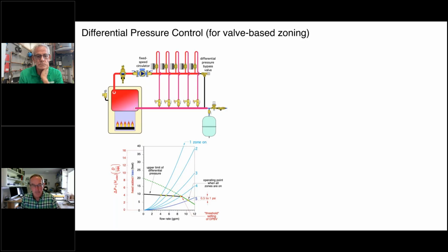We've been in projects where we could literally hear the noise through a zone valve outside a mechanical room with the mechanical room door shut. It was just buzzing or singing away. And obviously you don't want that. So one of the classical methods, dating back several decades, to compensate for that is to put in what's called a differential pressure bypass valve. This is a valve with a spring-loaded disc, and it simply opens at a certain setting pressure.